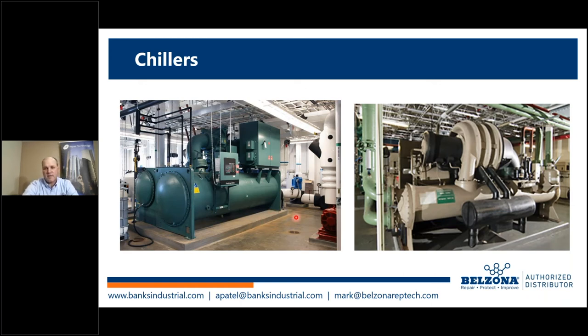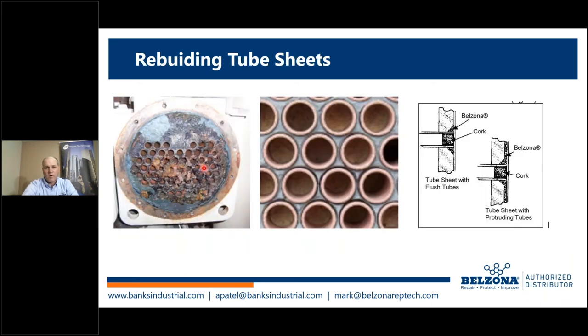So we've got the same kind of thing where we have water flowing through the tube sheet. This is an example of a tube sheet, and AJ talked about this before. You can see here, this is what it looks like. This is before it was sandblasted. This was all the loose corrosion on there. You take that off, you don't have a lot left. And once you lose this seal, you have a problem. So you can use Belzona. We can go ahead and make a repair to that.